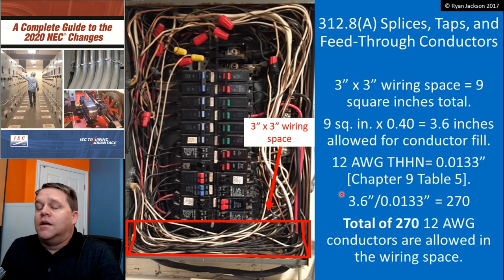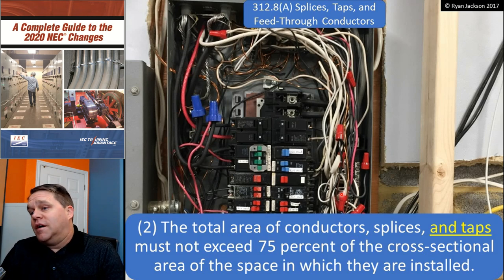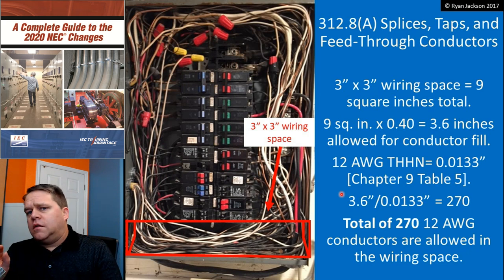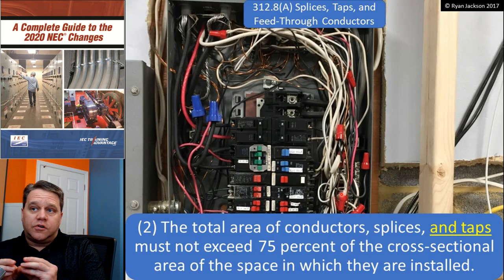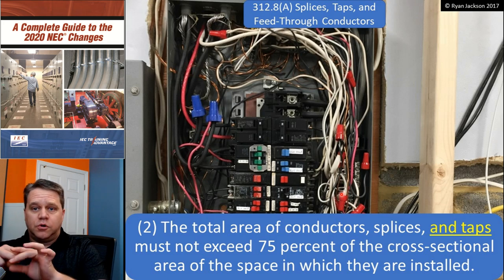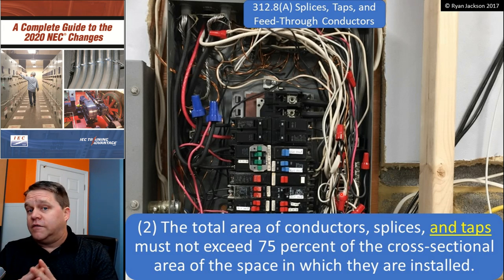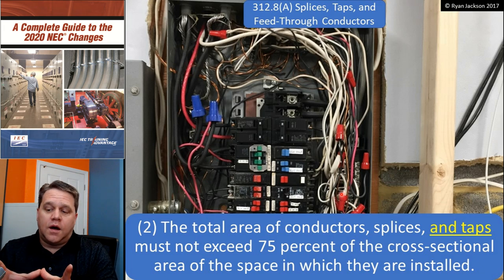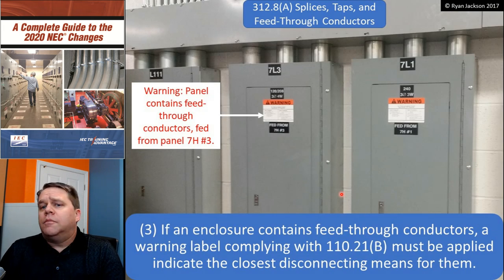A2: the total area of conductors, splices, and taps must not exceed 75% of the cross-sectional area of the space in which they're installed. So A1 says no more than 40% fill for conductors alone; A2 says conductors plus the splicing equipment — twist-on wire connectors, push-in wire connectors, all of those — must not exceed 75% fill. There is no way you're going to violate that. We saw that 40% fill is 270 twelve-gauge wires in a three-inch by three-inch space.